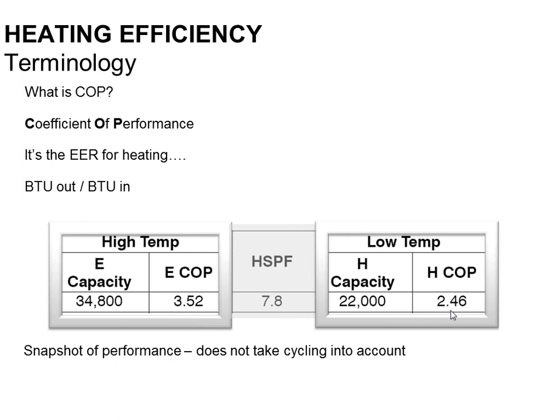So electric heat is 1.0, furnaces are 0.8 to 0.98, heat pumps are 2 to 4 COP, depending on the outdoor air temperature. But even at the 2 number, right, 2.46 on the right-hand side at 17 degrees over here, that's still 250% compared to 98% efficient on a furnace. So it's 2.5 times more efficient than the absolute best furnace you can buy. Every single heat pump, even the worst heat pump ever made, is more efficient than the best furnace or boiler ever made. Now, it doesn't mean it's the cheapest thing to run, right, because gas is pretty cheap around here, but it is the most efficient thing to run. We got to look at some other factors to see which one's less expensive to run in terms of money.